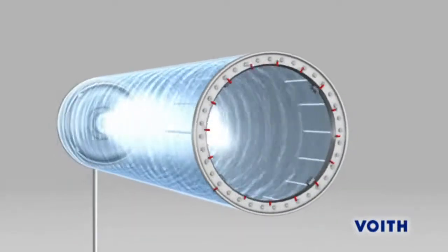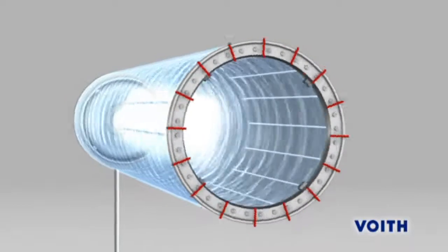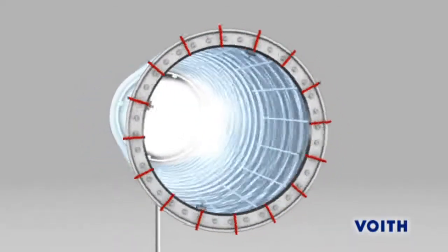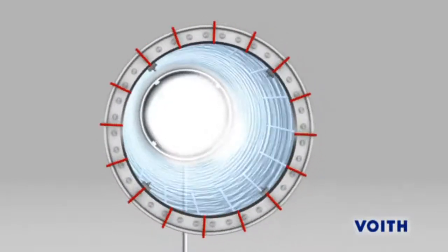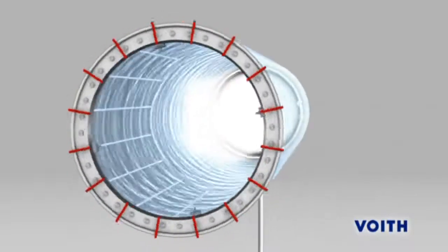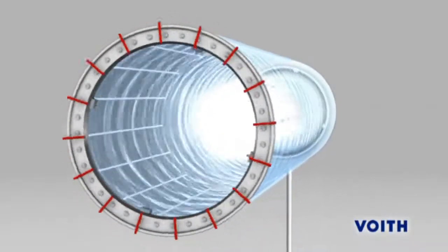From a speed of approximately 400 meters per minute it forms a water rim which is then stabilized at approximately 500 meters per minute. From now on the turbulences in the condensate are reduced drastically and the heat transfer to the dryer is reduced.